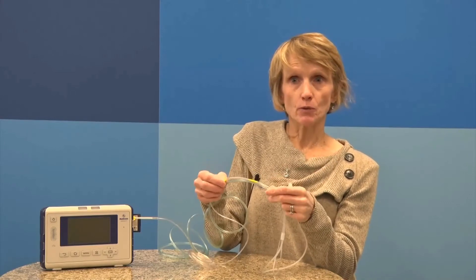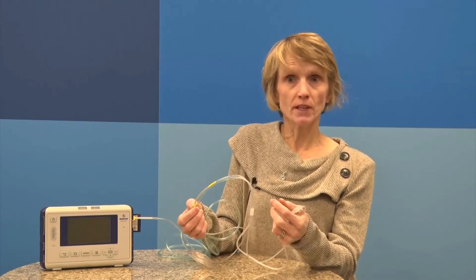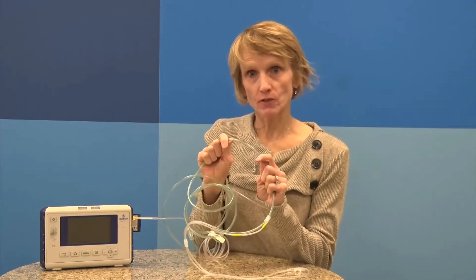The dryer was also lengthened to increase the usable life of the sampling line. Increasing the ability to absorb moisture will increase usable life and therefore may reduce the number of times lines need to be replaced due to moisture buildup. Additionally, modification of the internal geometry of the tubing used for oxygen delivery is now expanded throughout the length of the tubing to reduce kinking, allowing for continued airflow at greater than 75% of the flow rate, ensuring a continuous oxygen supply is maintained to patients requiring supplemental oxygen if lines become kinked.